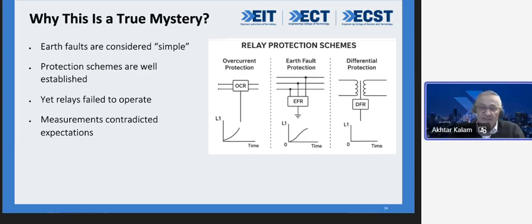The fourth thing in this particular measurements area I can mention is the topologies, which is the uncalculated system topology. So from a passive network, you're going to an active network. That is, now you've got inverters and distributed generation, and they are all going to impact and alter your fault current. Therefore, your standard pre-calculated setting becomes ineffective. So that's all on the measurements part.